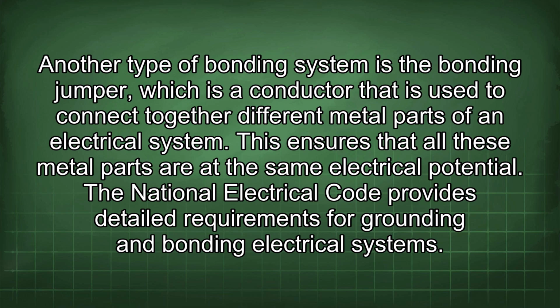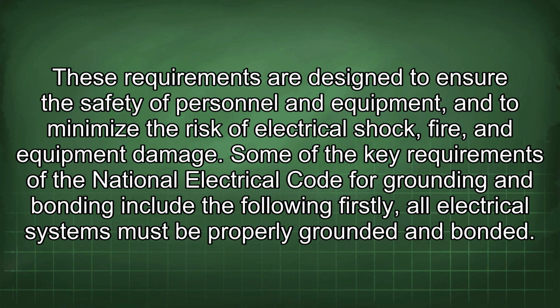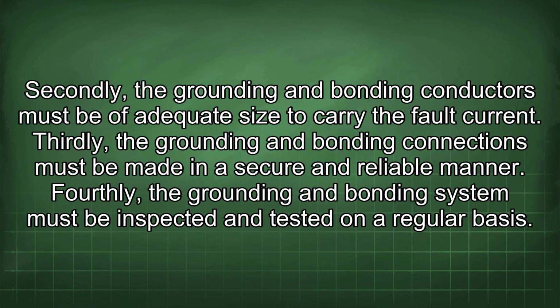The National Electrical Code provides detailed requirements for grounding and bonding electrical systems. These requirements are designed to ensure the safety of personnel and equipment and to minimize the risk of electrical shock, fire, and equipment damage. Some of the key requirements of the National Electrical Code for grounding and bonding include the following. Firstly, all electrical systems must be properly grounded and bonded. Secondly, the grounding and bonding conductors must be of adequate size to carry the fault current. Thirdly, the grounding and bonding connections must be made in a secure and reliable manner. Fourthly, the grounding and bonding system must be inspected and tested on a regular basis.